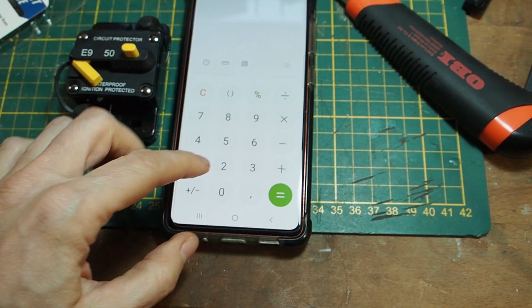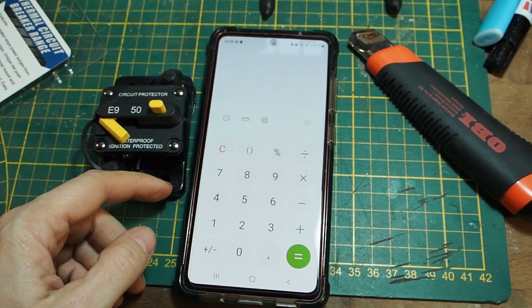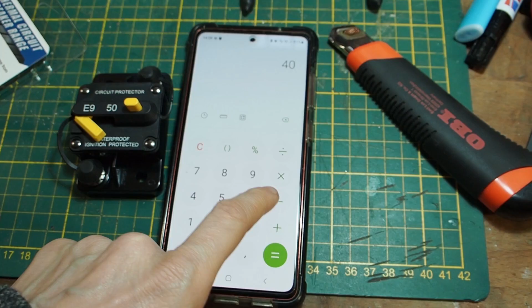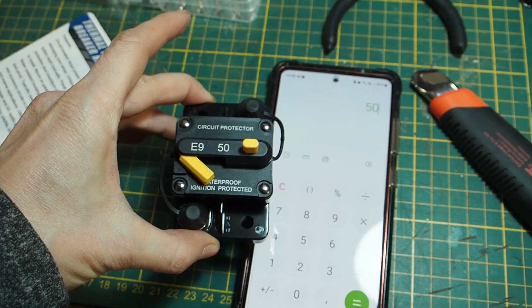So usually to size a breaker, you size it 25% bigger than your actual amperage. So 40 amps is what we get from the solar charge controller, times 1.25 is 50 amps, and this is what I'm using here.